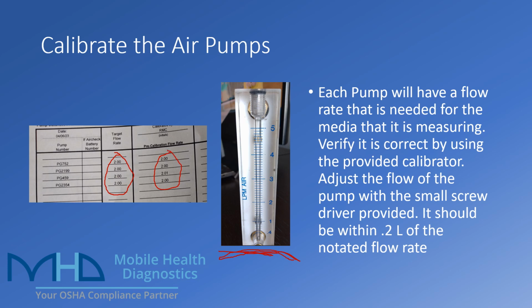So what we're going to be doing here, in the process of calibrating, is matching up that those serial numbers are indeed calibrated to the flow rate that we want for the collection media that they're rated for. If you need to, use a small screw on the pumps that adjusts the flow rates, and the end goal is to get them within 0.2 liters of the notated flow rate on the actual pump sheet.